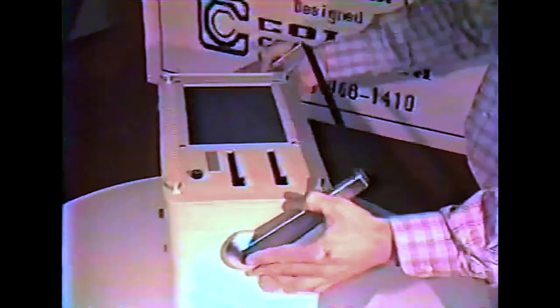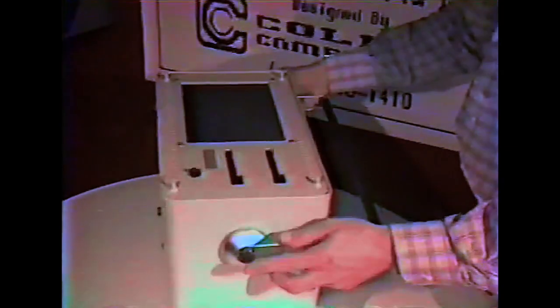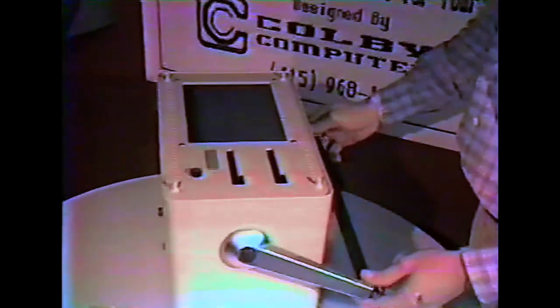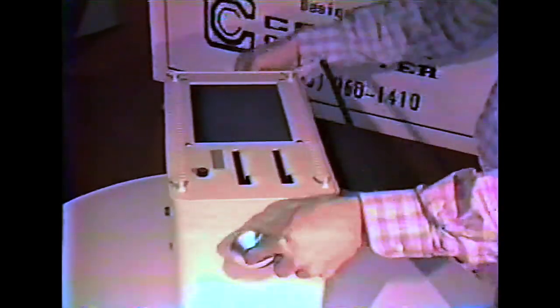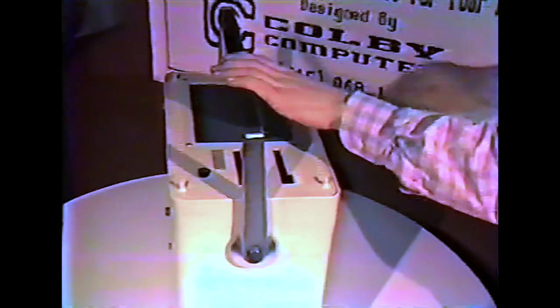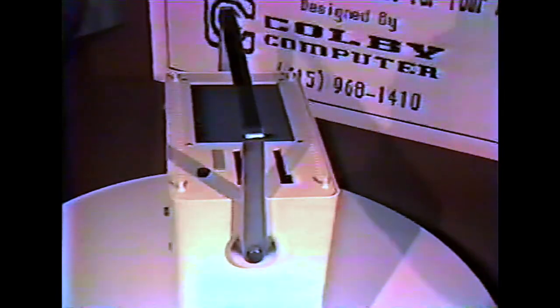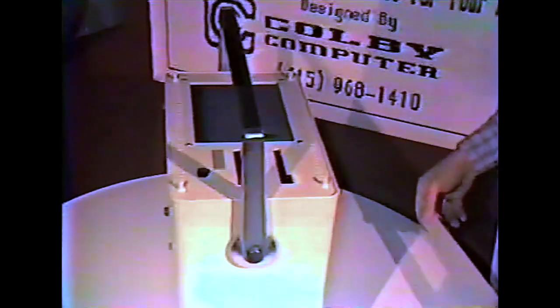To move the handle, both buttons must be depressed, and then the handle can be moved to any one of the locking positions. When it's put into the position desired, moving the handle back and forth will cause both buttons to pop, indicating that the handle is locked on both sides.